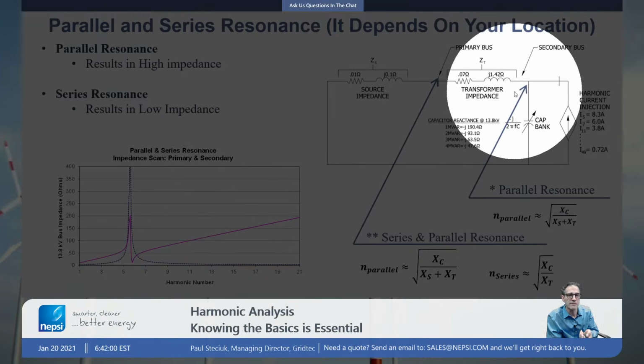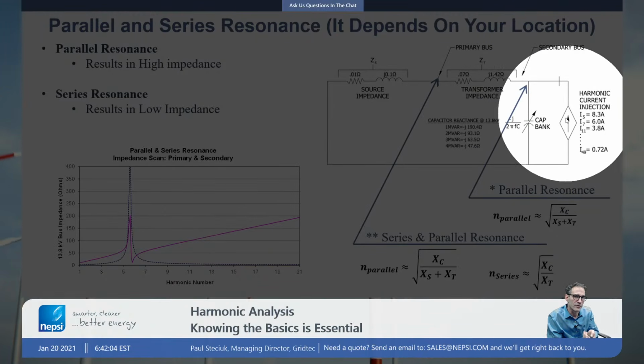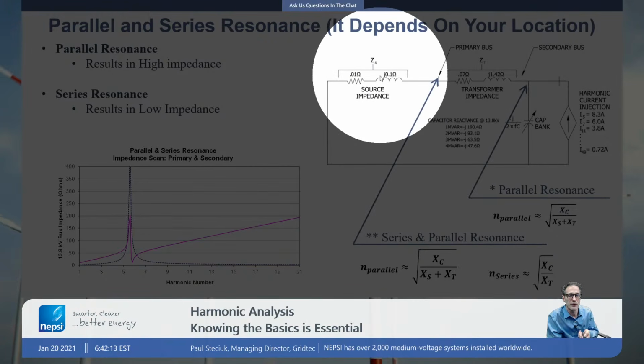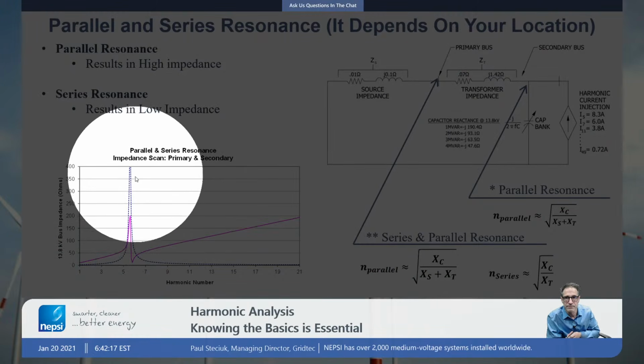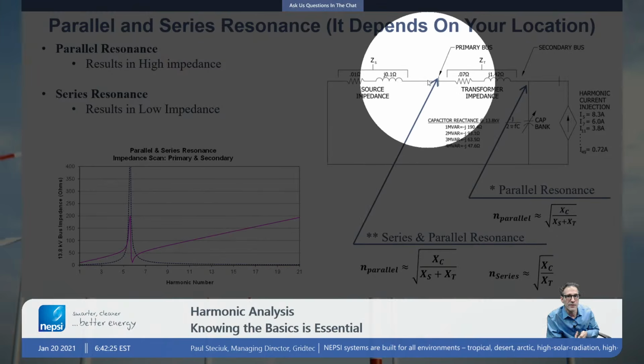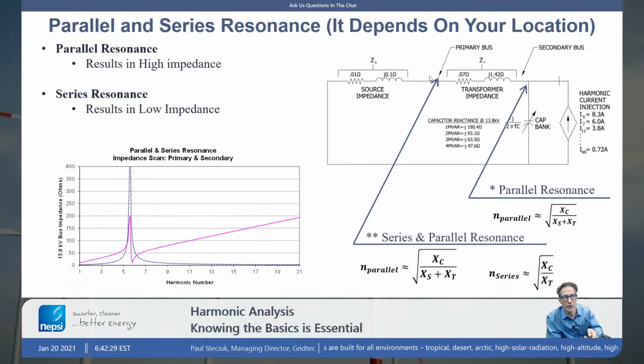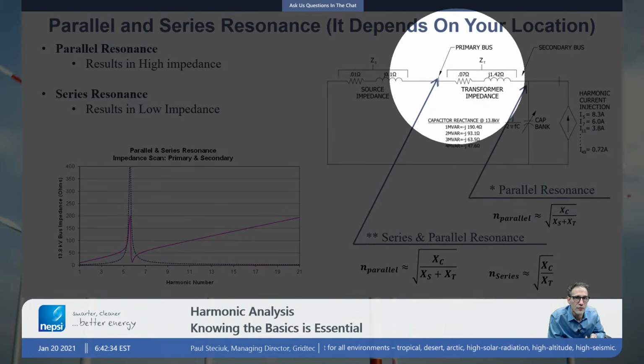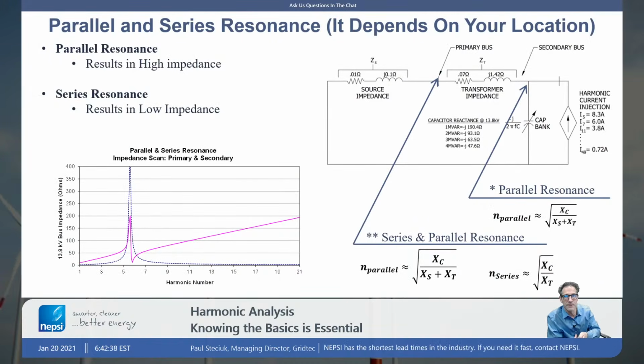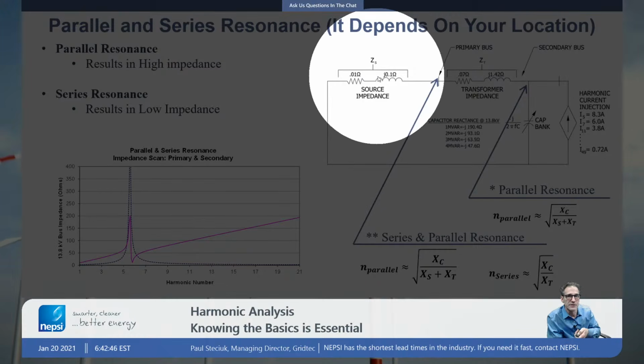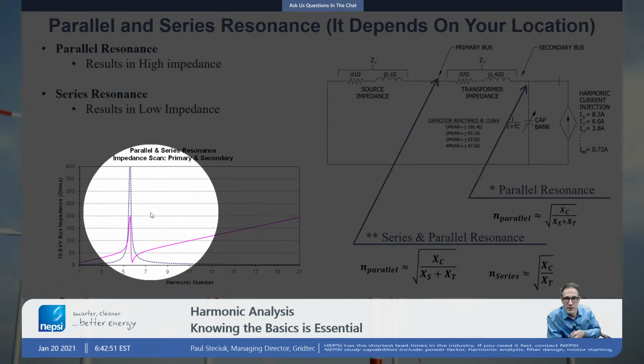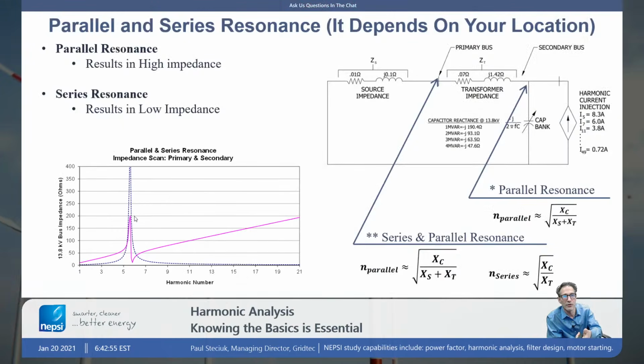Depending upon where you are in a network, you sometimes have what's called parallel resonance and series resonance. So looking from the drive here, or that current injection point, into the circuit, we have parallel resonance. This capacitor here is in parallel with that impedance here, causing parallel resonance. And that's that blue dashed line down here. The magenta line, though, is us standing here and looking into the network. In this case, we have both series and parallel resonance. We have the series resonance where we've got this transformer impedance in series with the capacitor, creating a series impedance, and that represents the low point on this magenta curve. And then we have the source impedance here, which is creating a parallel resonance, and that would be represented by the peak here. So we have both a parallel and series resonance.